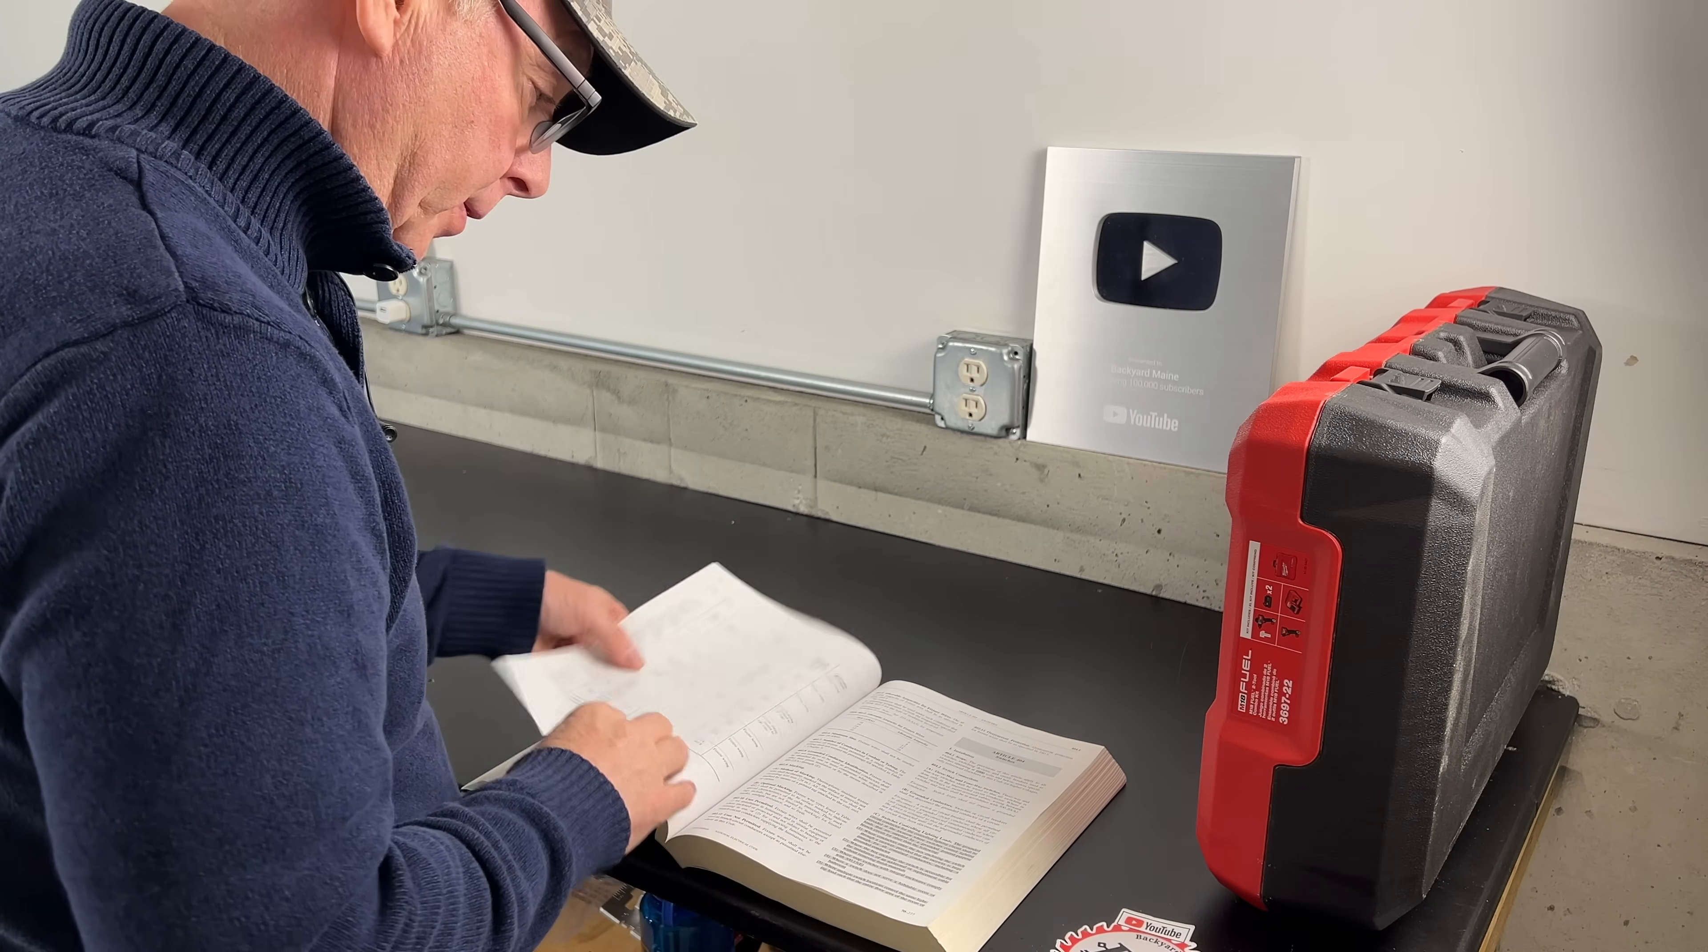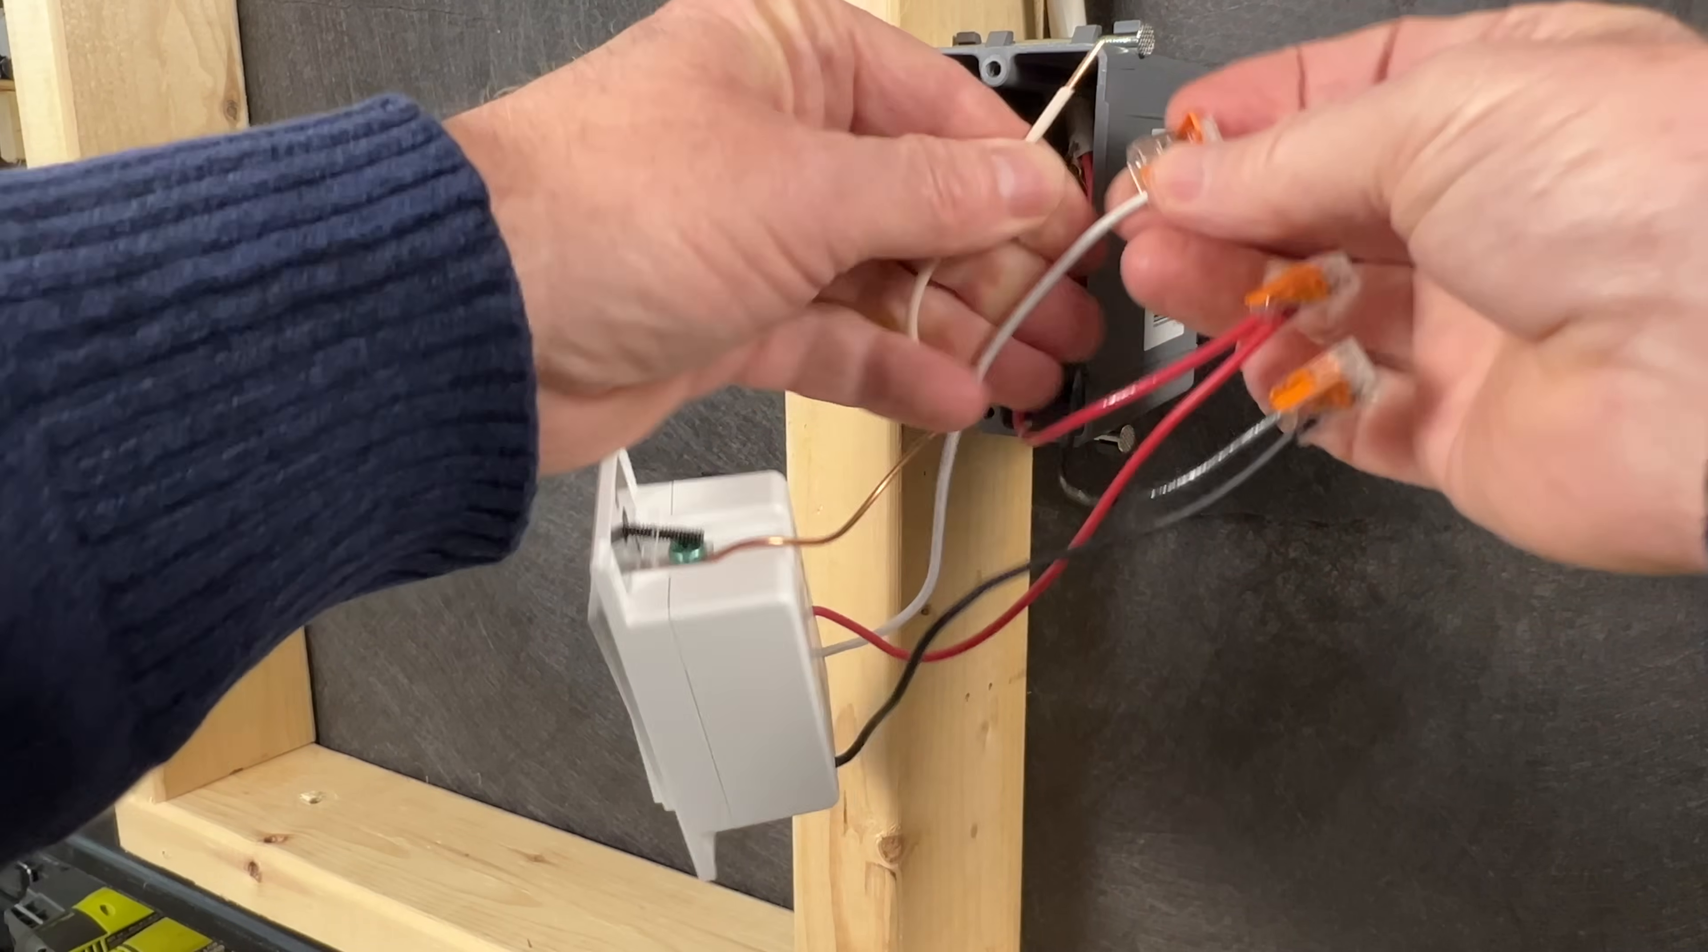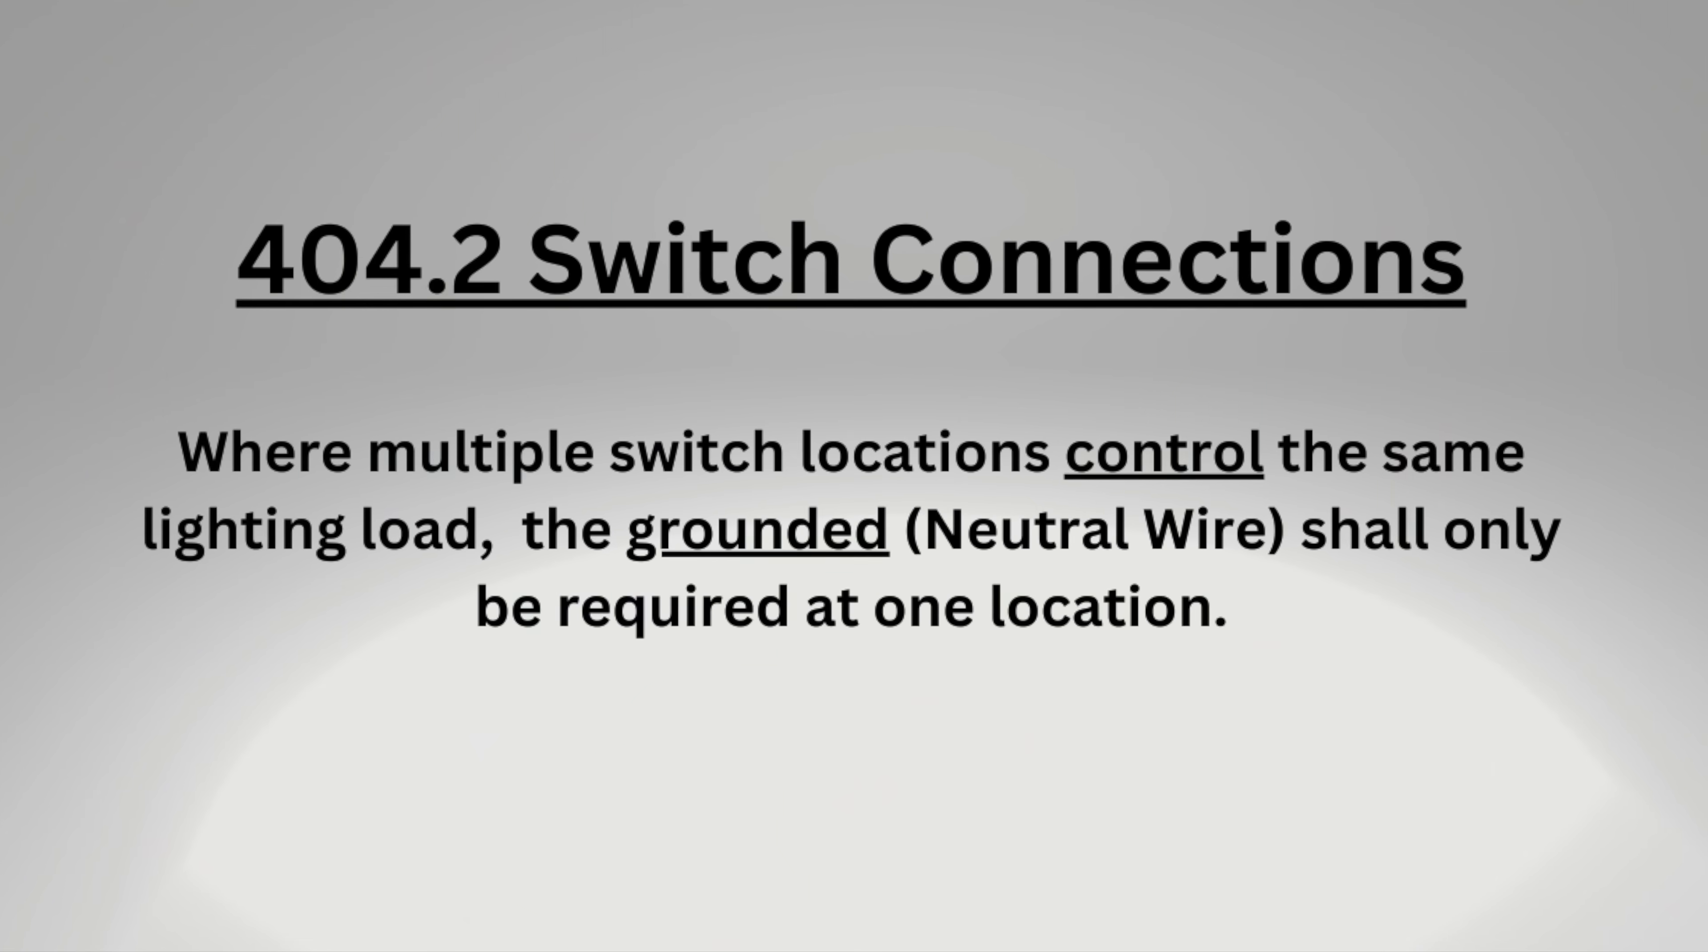Let's go to the code book. All the way back in 2011 article 404.2 of the NEC was updated to require a neutral conductor at light switches. The reason for the update was many new lighting controls and smart switches were being introduced which required a neutral wire to keep the electronics functioning. But article 404.2 also states that where multiple switches control the same lights a neutral wire is only required at one of the switches. So this means with three-way and four-way switches at least one of them will require a neutral conductor making the California three-way an obsolete method.